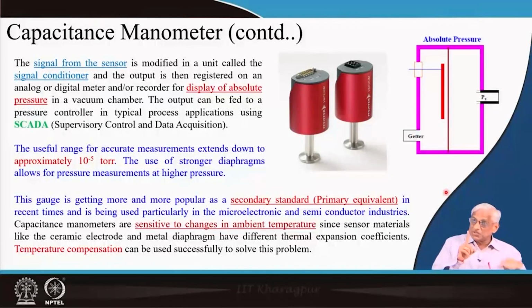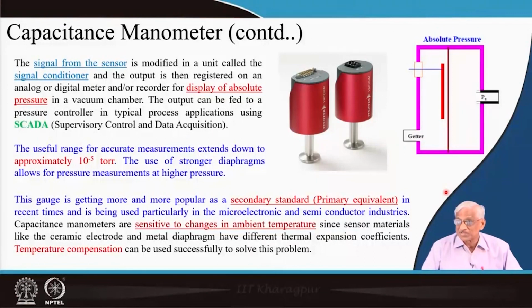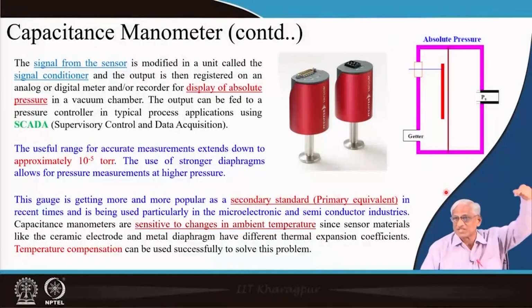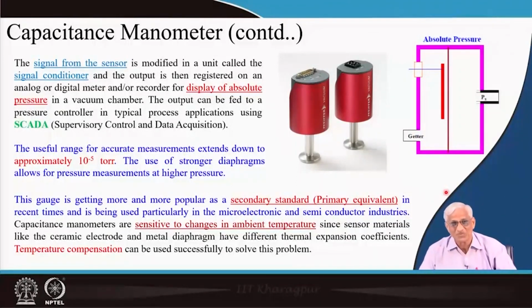But temperature should be constant. If you make a measurement and after some time the pressure reading has changed, the pressure might not have actually changed - temperature may have changed, causing some deflection change. So throughout the pressure range of your experiment, temperature should be maintained constant. Even if temperature is not constant, another sensor can measure temperature and temperature compensation can be done electronically - these are smart sensors today, with a lot built in.